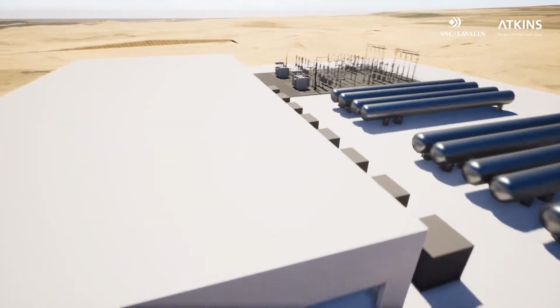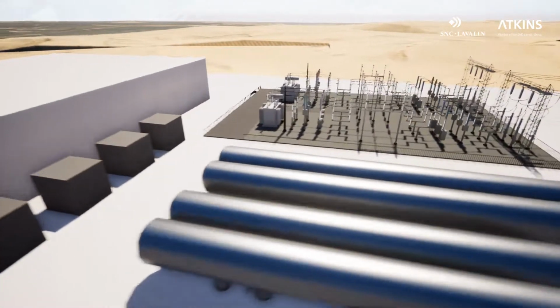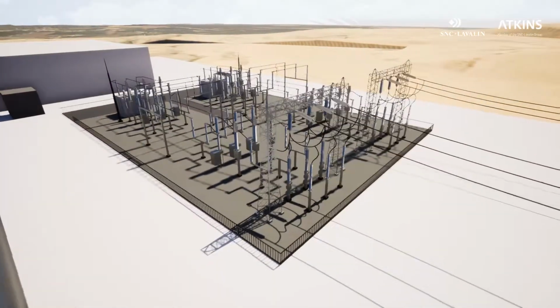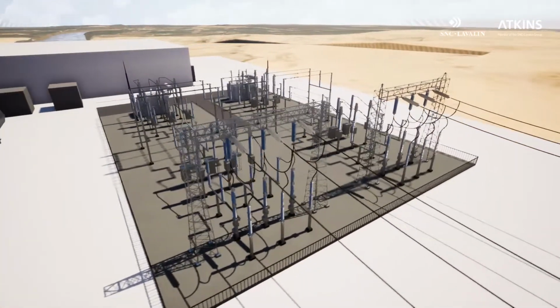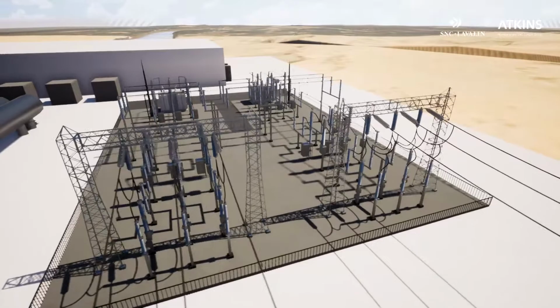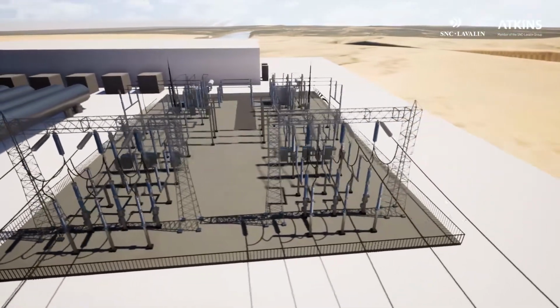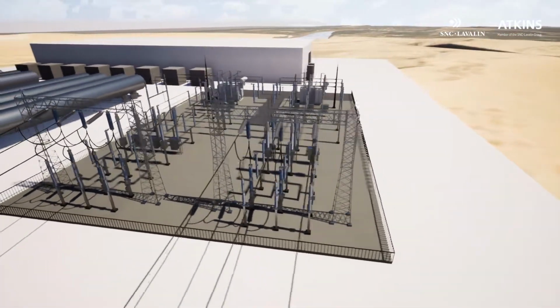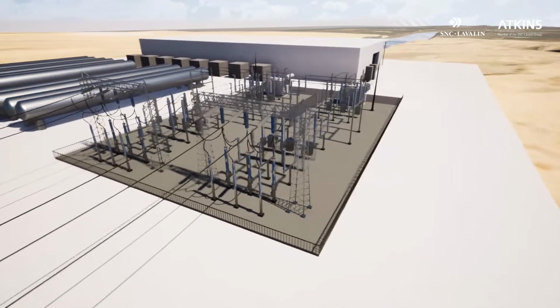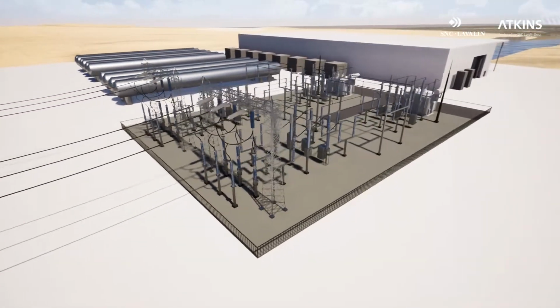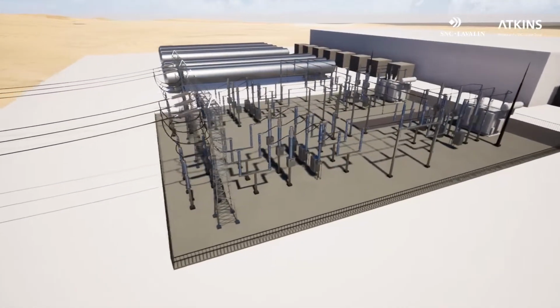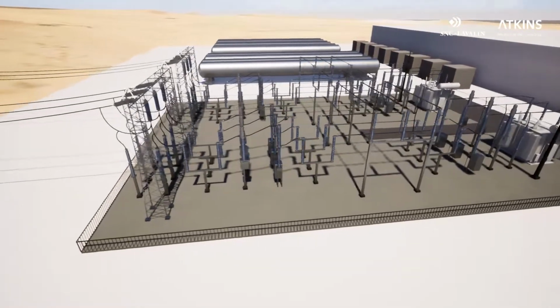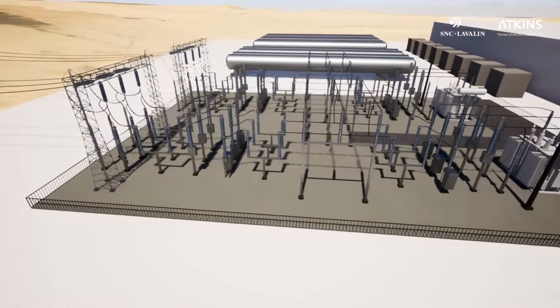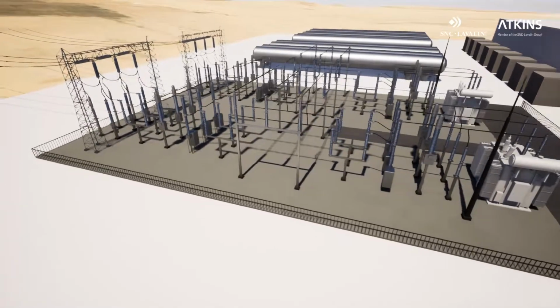The proposed design of the electrical systems prioritizes reliability, availability, and easy maintenance of the pumping station. The 300 megawatts power demand of the pumping station will be met by a new connection to the Egyptian national grid. A new open switchyard will be constructed adjacent to the pumping station building to receive power from the grid. The dual circuit connections are fully rated and have a cross connection to ensure that there is no loss of pumping capability, even in the event of maintenance or repair.